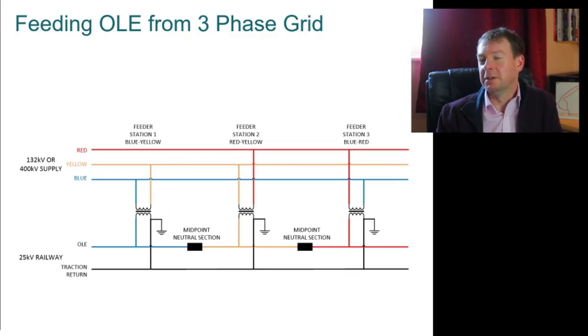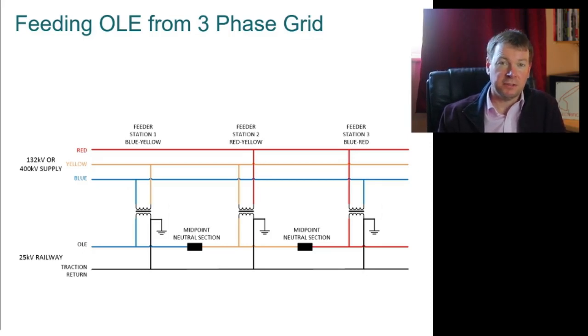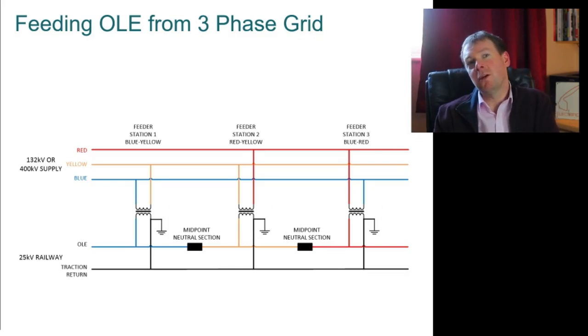So we feed the trains at single-phase, but we're feeding from a three-phase national grid. If we just took all of our supply from the same two phases at every feeder station, we would unbalance the national grid so much that your domestic supply would start misbehaving, frequencies would wander off, motors in factories would start running backwards. It would not be good. For that reason the national grid imposes strict limits on the railway as to how much imbalance we're allowed to impose. So at each feeder station down the railway, we take our supply from two different phases.